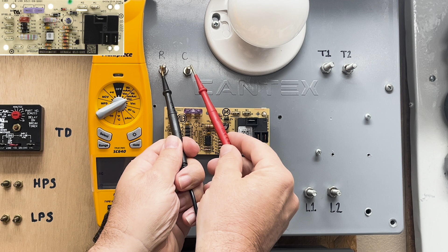With that, I'm going to go ahead and wire up the load first, not going through the relay on the board, just to demonstrate. The load does need 240 volts, which is both legs of the power. I'm going to go ahead and take L2 and wire it up to T2, then take L1 and wire it up to T1.